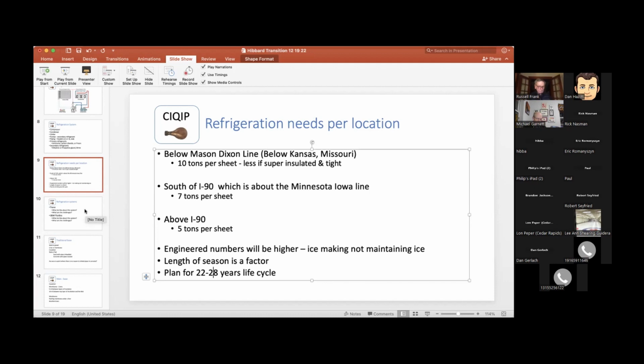Okay, a 60-ton chiller, because when you go to a manufacturer and you order a chiller, you're ordering it in nominal tons. And then you tell them to design it for a certain operating temperature, and that tells you what your tonnage is going to be. But for our application, it's very nice because it's simply about half what a nominal ton is. So a 40-ton chiller will be 20 for ice making.